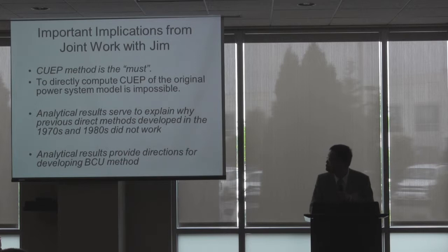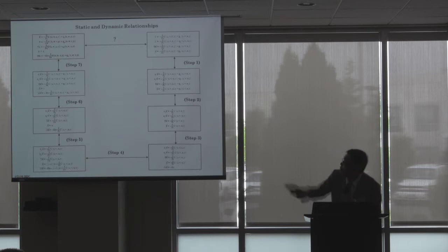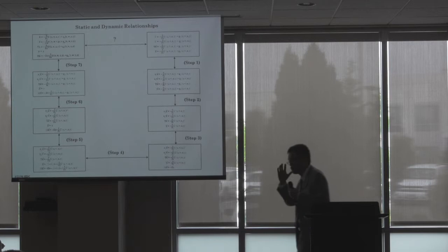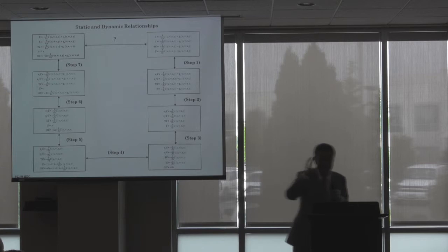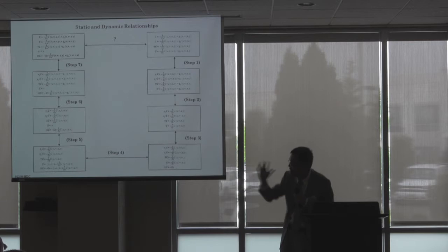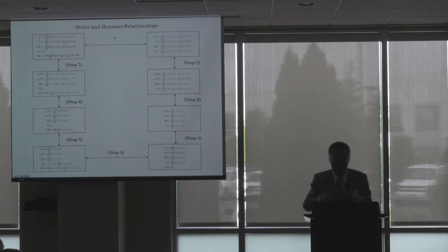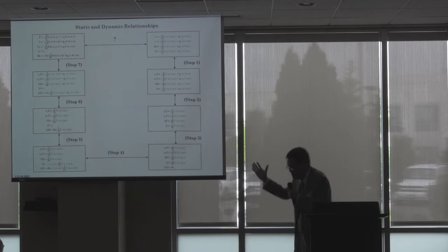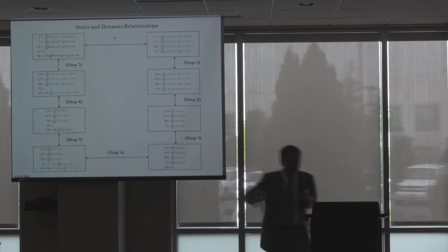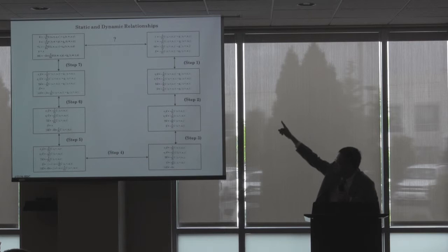That's why we pointed out the direction of the BCU method. For the original power system model, it's impossible to compute the controlling UEP. So we define an artificial reduced model that tries to capture some static and dynamic relationships of the original model. We compute the controlling UEP of the reduced system and then map back to the original system — after seven steps. Under certain conditions, you can prove the reduced system's controlling UEP corresponds to the controlling UEP of the original system.